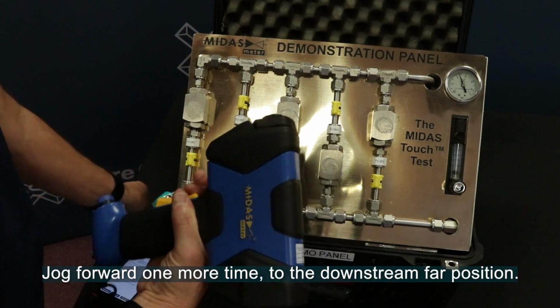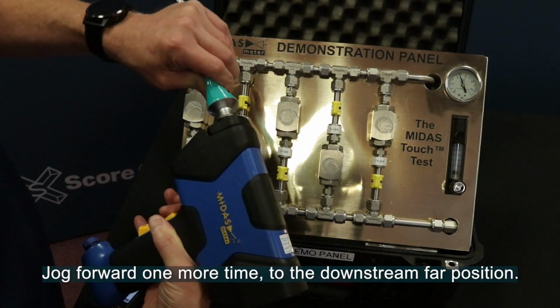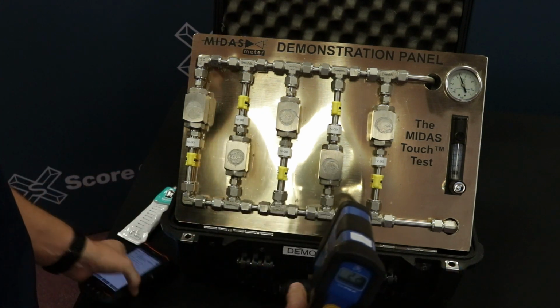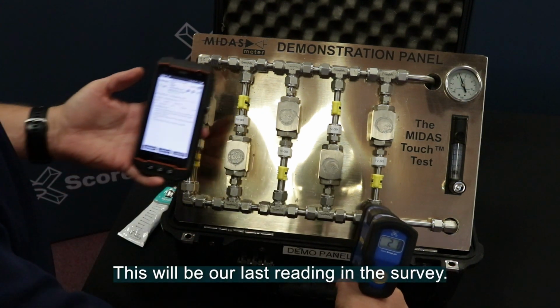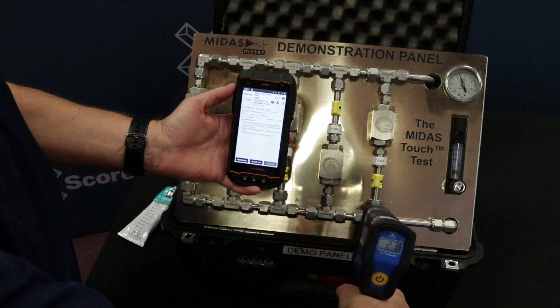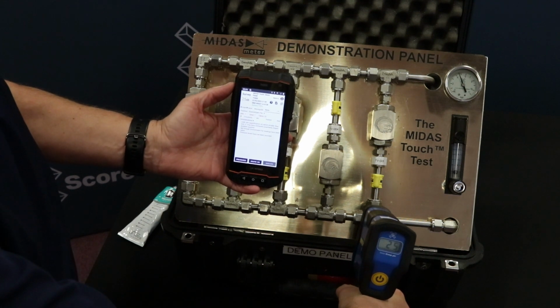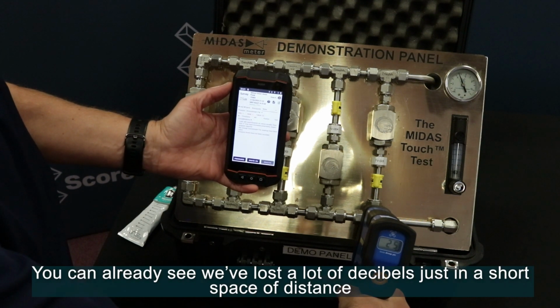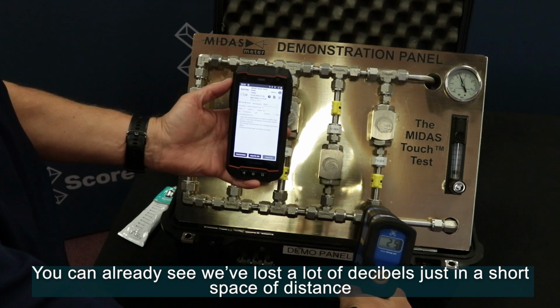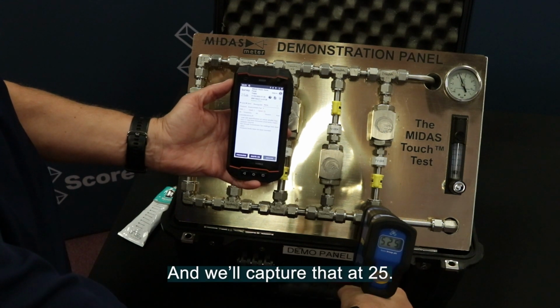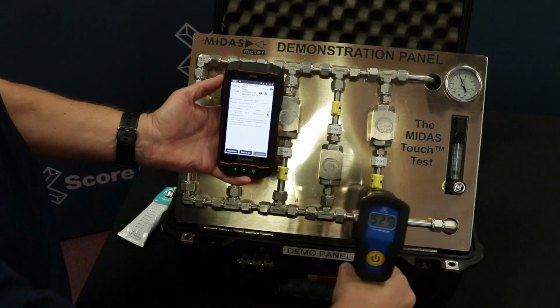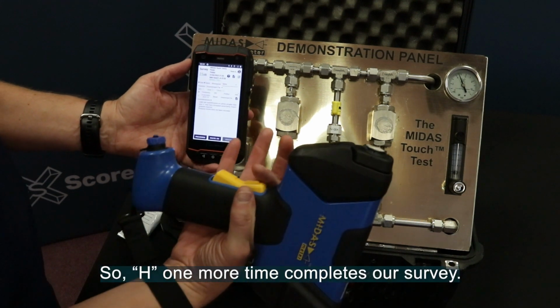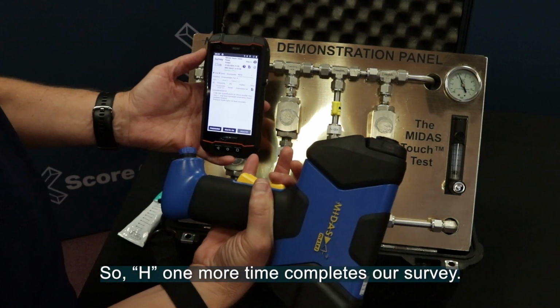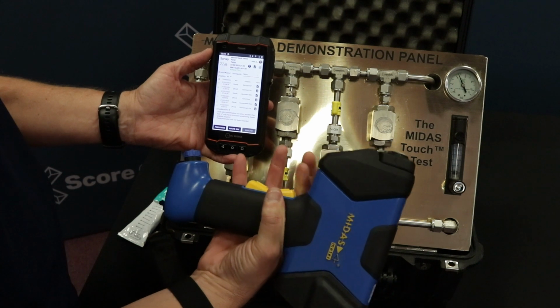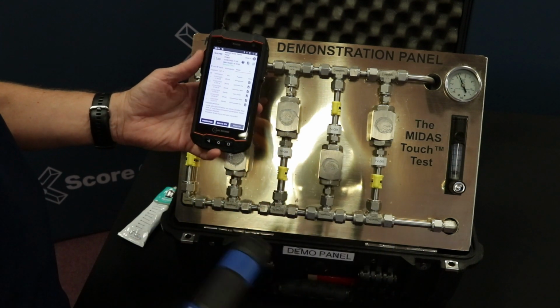Jog forward one more time to the downstream far position. This will be our last reading in the survey. You can see we've already lost a lot of decibels just in a short space of distance. And we'll capture that at 25. So, H one more time completes our survey. You hear a double beep.